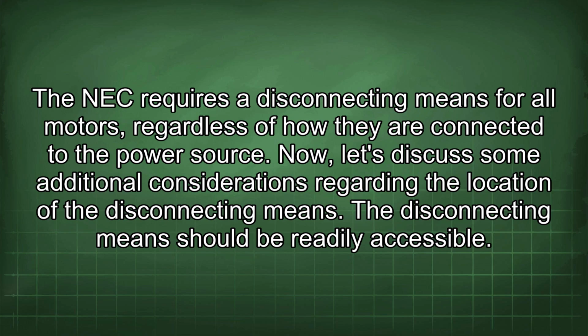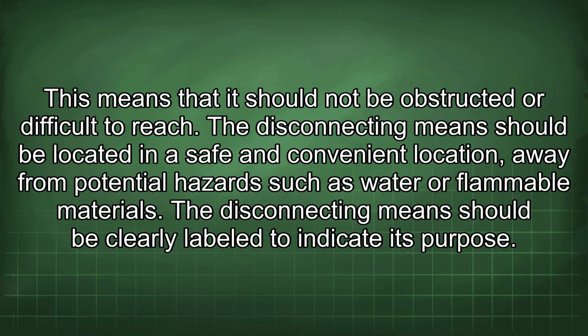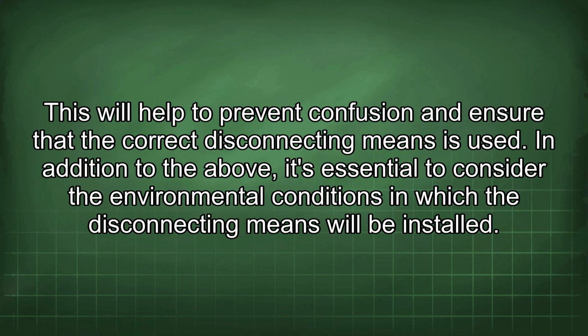Now let's discuss some additional considerations regarding the location of the disconnecting means. The disconnecting means should be readily accessible. This means that it should not be obstructed or difficult to reach. The disconnecting means should be located in a safe and convenient location, away from potential hazards such as water or flammable materials. The disconnecting means should be clearly labeled to indicate its purpose. This will help to prevent confusion and ensure that the correct disconnecting means is used.